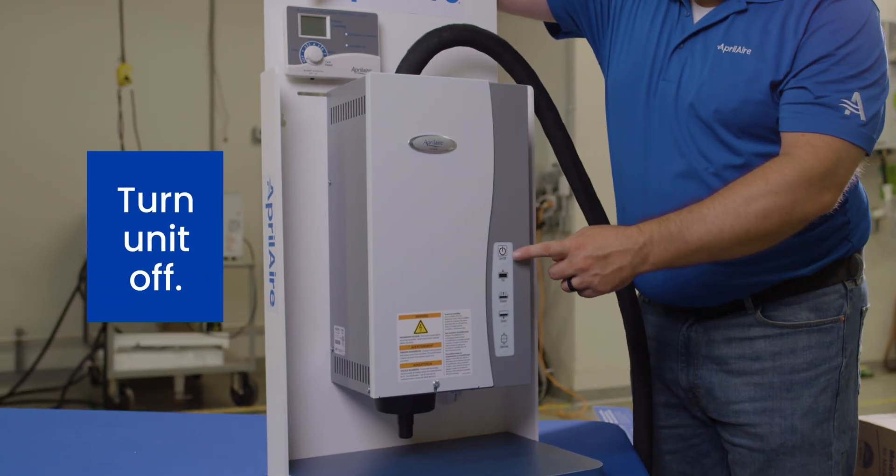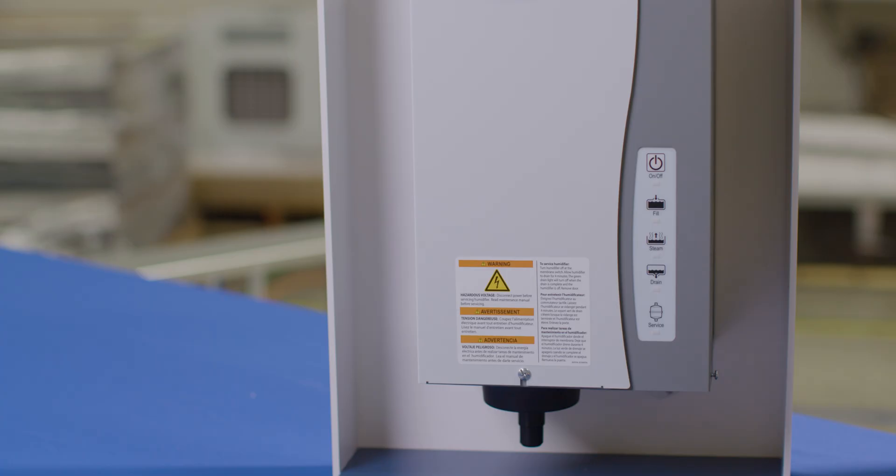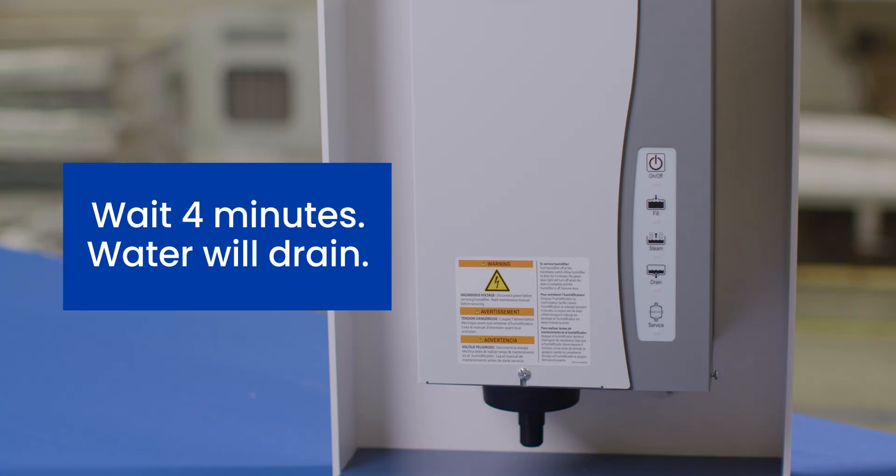The first thing you're going to want to do is turn the unit off, which will force the unit to drain. When you push the off button, you'll hear the solenoid valve open, putting cold water down the drain. Then the drain valve will open and let the water run out of the canister. Wait four minutes to make sure all the water is out of the unit.